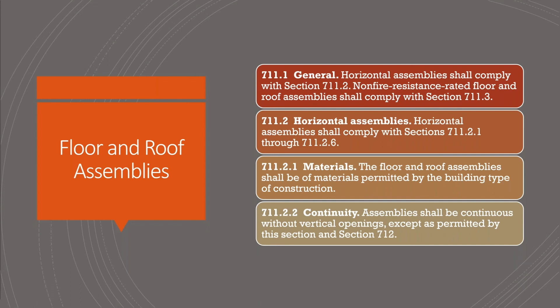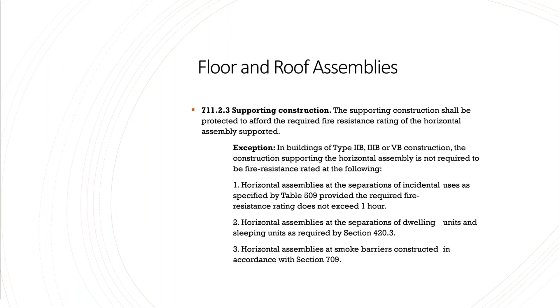So you've got your rated floors, your rated floor ceiling assemblies. When they hit the exterior, that's got to be carried all the way through the 2 layers, right? You don't just end at that first layer of the exterior wall; it goes all the way through to the interior sheeting of the exterior wall. So your continuity for horizontal assemblies is the same, just like your walls. Supporting construction we already talked about. To reiterate, whatever's holding up that horizontal assembly has to be supported the same as what that horizontal assembly is required to be rated at.